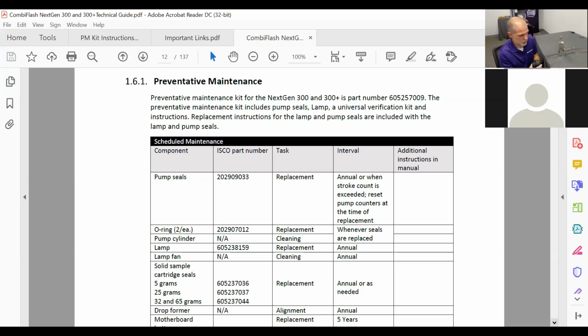Okay. Speaking of the pump cylinder, anytime you replace the seals, we do recommend a slight flush of that cylinder. If you've got solids in there, scratches, gouges, or anything like that, you want to see those. You want to clear them out if you can. When you replace the seals, you can ruin a seal right away by having stuff in your cylinder. So if you have a squeeze bottle with some IPA or some methanol or something, just go ahead and squeeze it out into that cylinder, get it nice and flushed out.